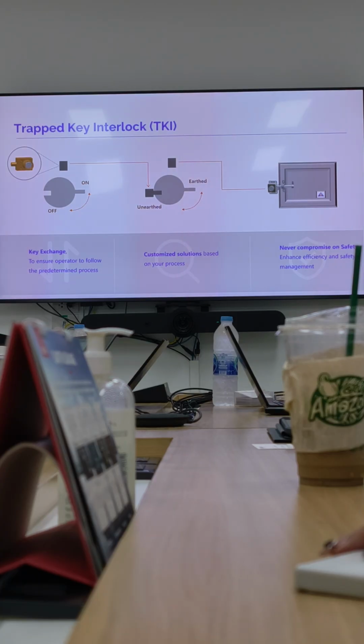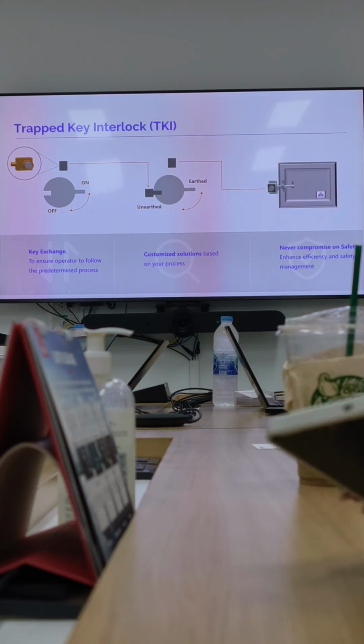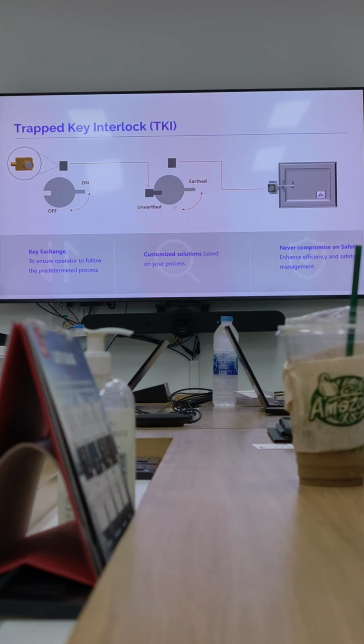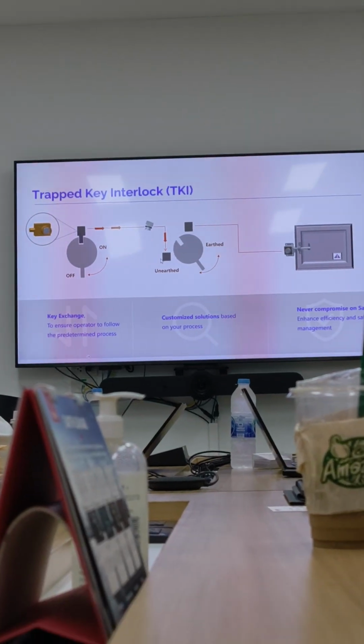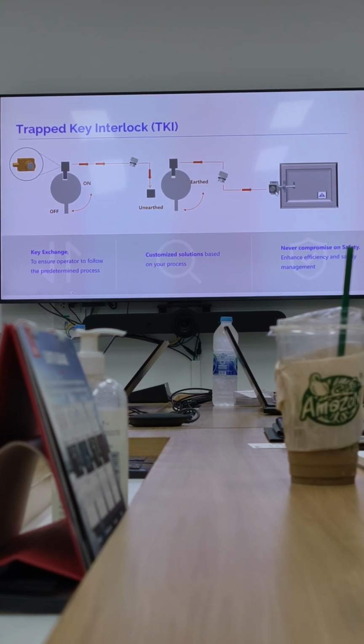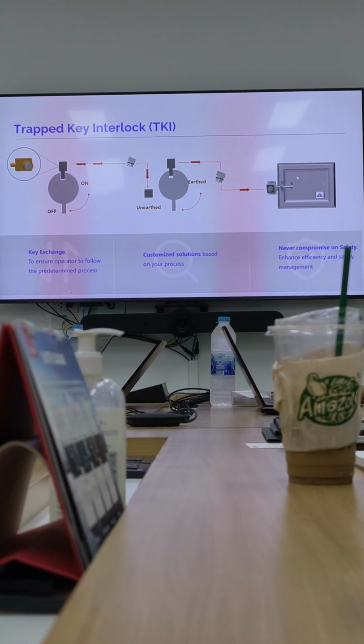This shows another example of how the interlock works, on the switch gear - the isolator, VCB or ACB. This part is on the earth switch, and this part is on the access. First we isolate the power, switch it to off position, and lock it. Once locked, there's a key here. We take the key, go to the switch, unlock it, set it to earth position, and lock it. Then there's another key that goes into access, so we can safely operate this.